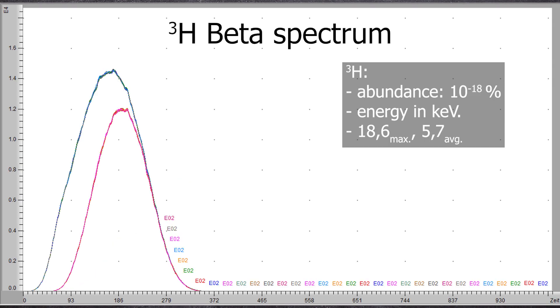Let's look at the spectrum of tritium. We can see that this is significantly spread out in the low energy range. This is due to the maximum energy of only 19 kilo electron volts. The energy of the betas is sometimes not sufficient to ultimately generate strong enough light signals for all three detectors to register them. This leads to an increase in double coincidences.